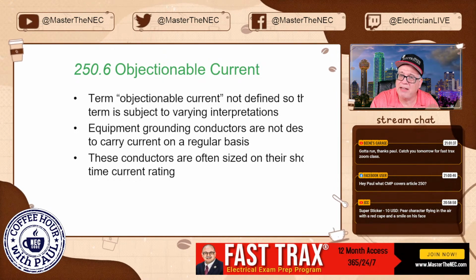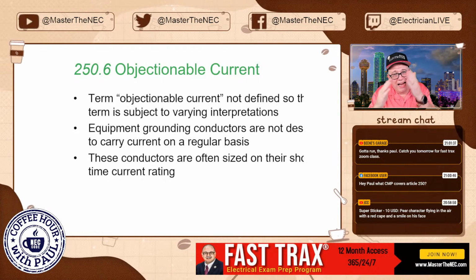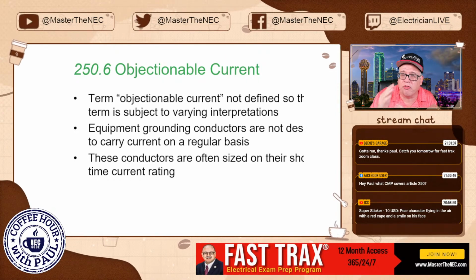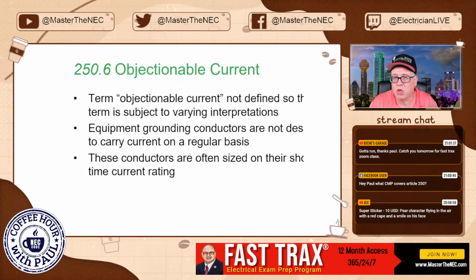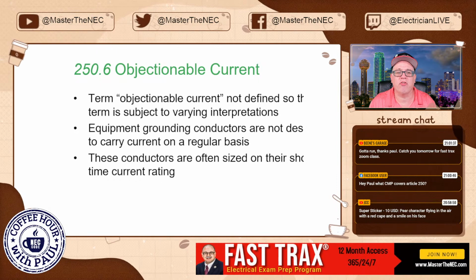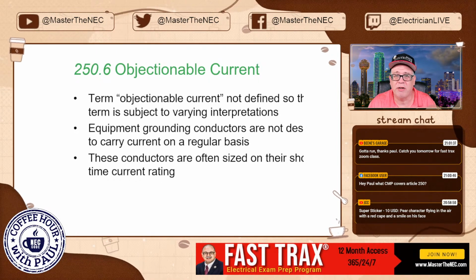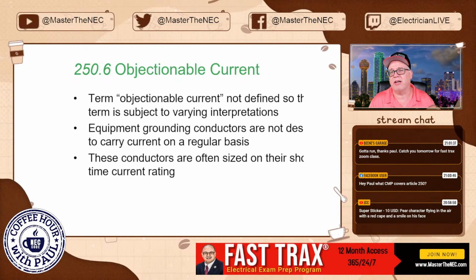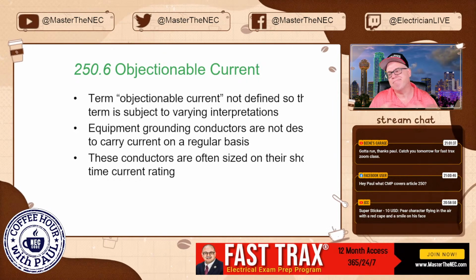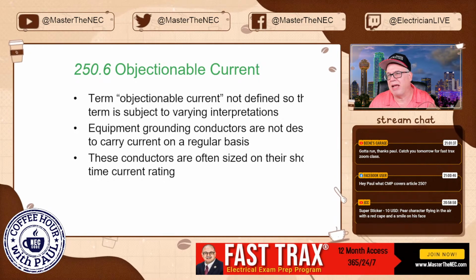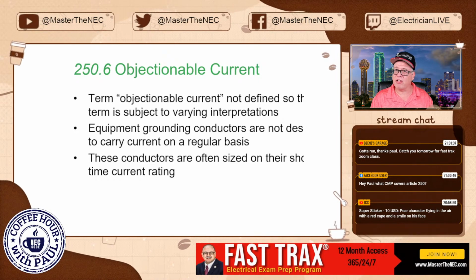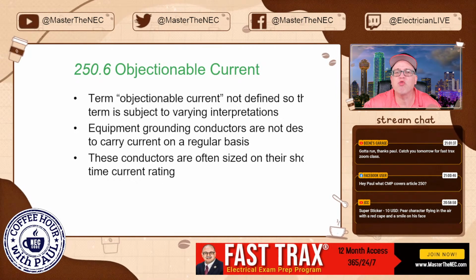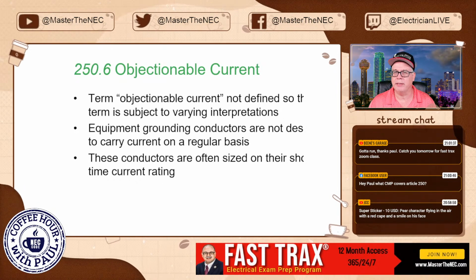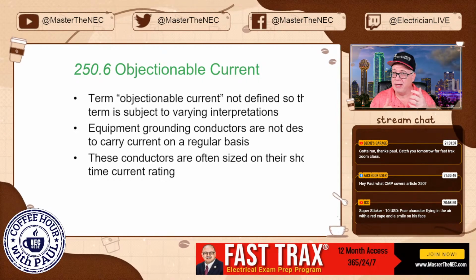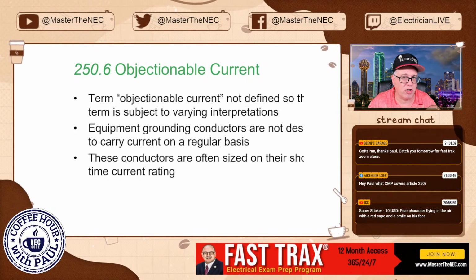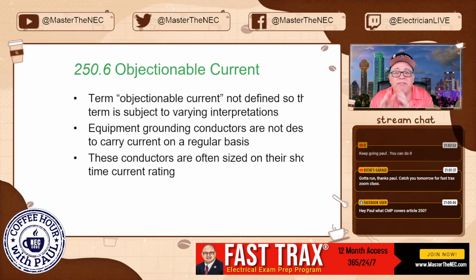So if I make an improper case to neutral downstream, where I don't isolate the equipment grounds and the grounded neutrals, then I create an example of objectionable current. And that circulating current can cause all kinds of problems, not just a shock hazard, but it also can cause issues with other electronic equipment and things like that. So again, that is kind of an example of objectionable current. And the code tells us that we've got to try to do something to remove that objectionable current. We can start taking some connections loose, but we cannot remove the effective ground fault current path. So we've got to analyze the system very well.